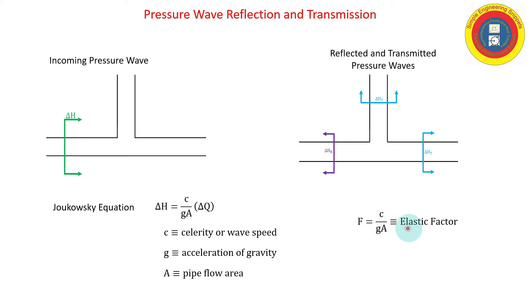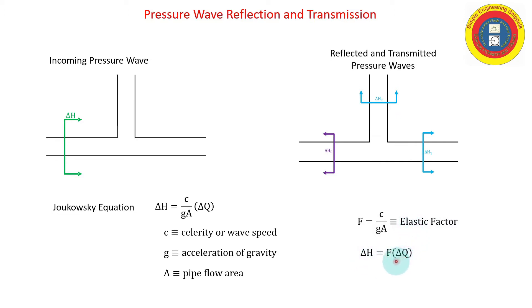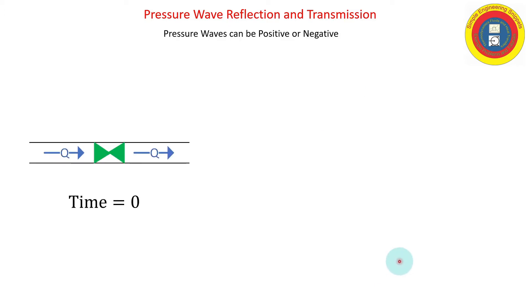We're going to refer to that grouping as the elastic factor and give it the symbol F. In general, F could be different in each one of the pipes at the junction. We will be writing the Joukowski equation as: delta-h equals F times delta-q.